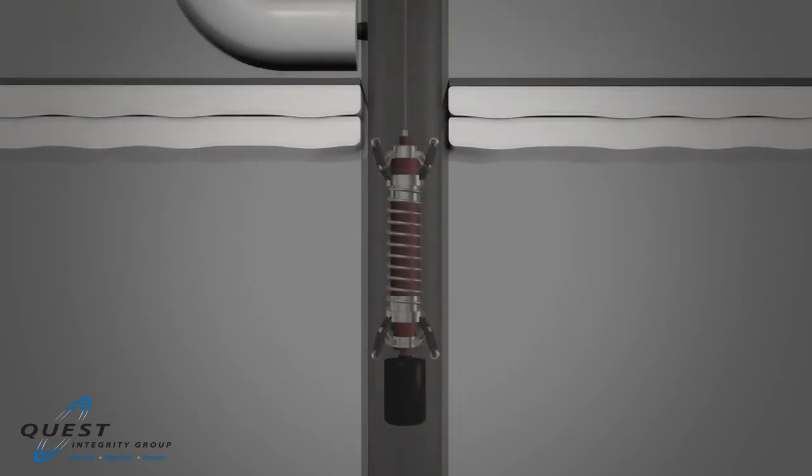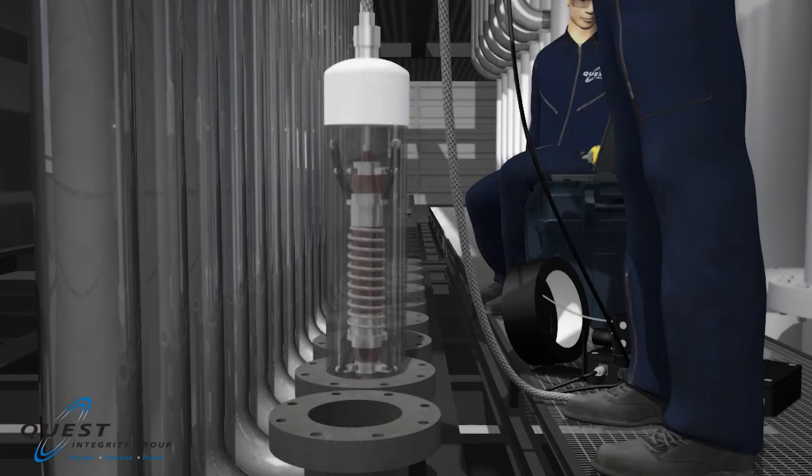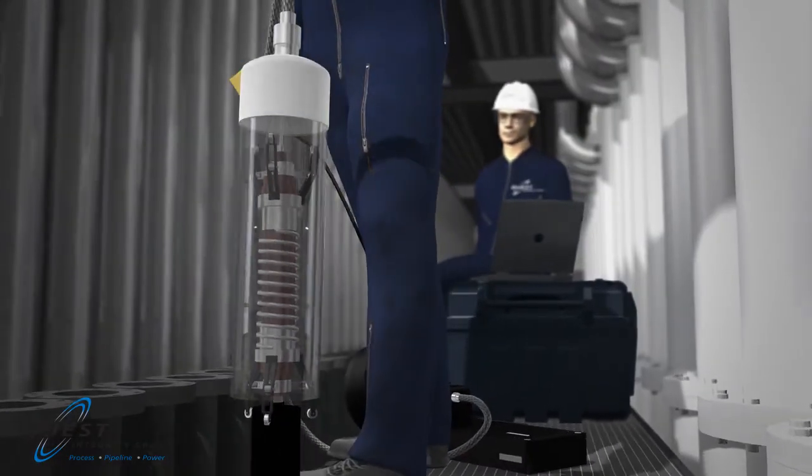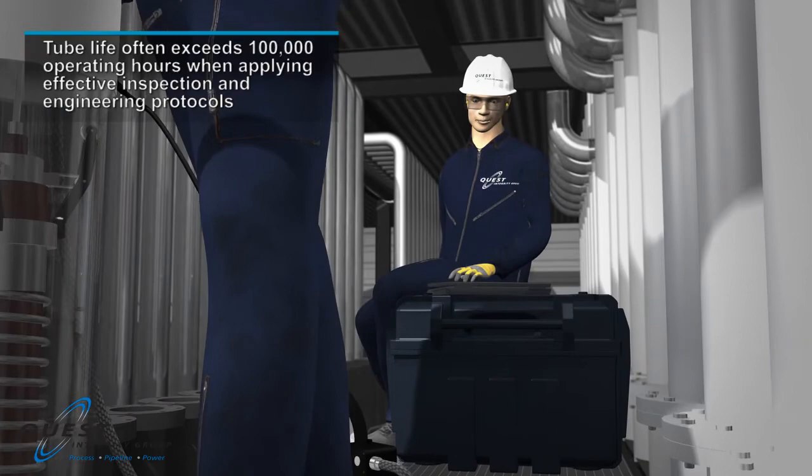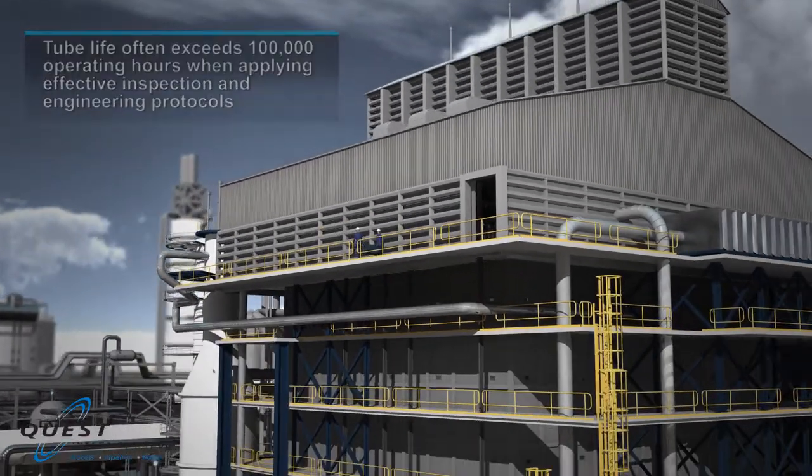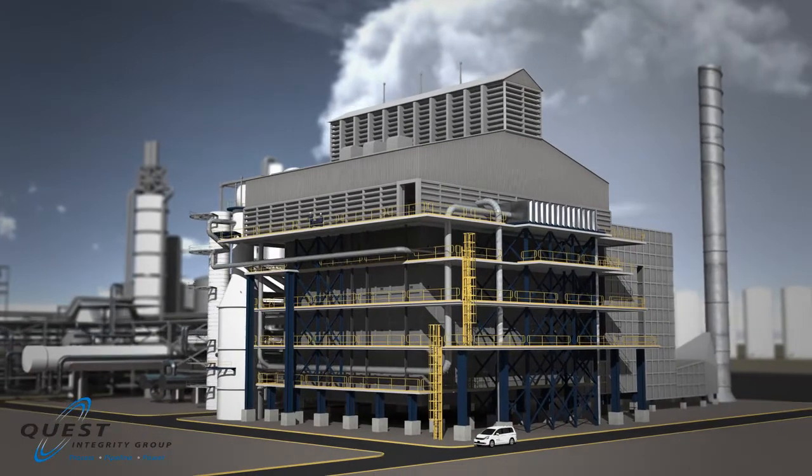The LOTUS inspection is completed quickly. The collected inspection data enables a level 1 life assessment to be performed directly afterwards. The LOTUS test results provide a significant quantity of diagnostic information, allowing plant engineers to manage and often extend tube life beyond the typical prescribed normal 100,000 operating hours. This information also assists plant operators in improving reformer output while operating within the integrity window.